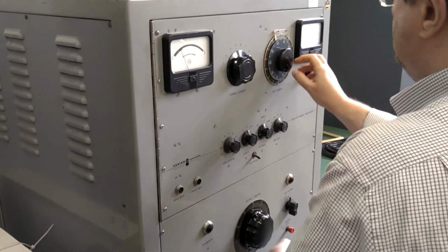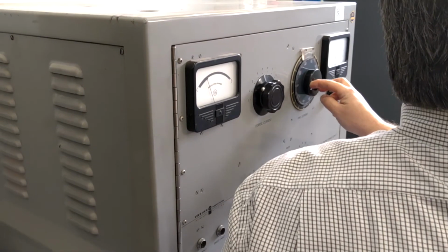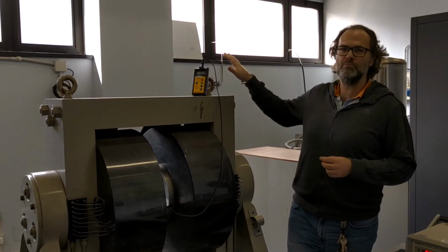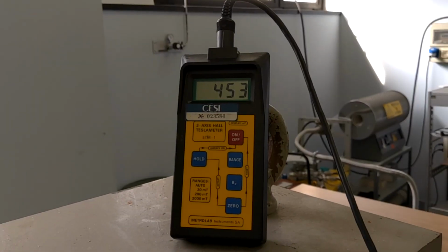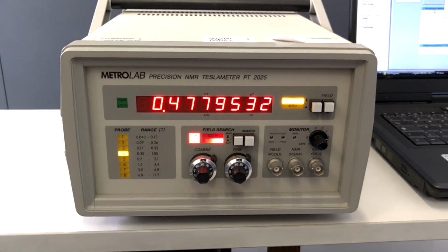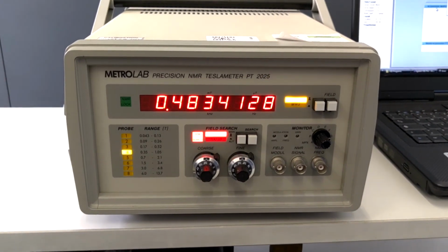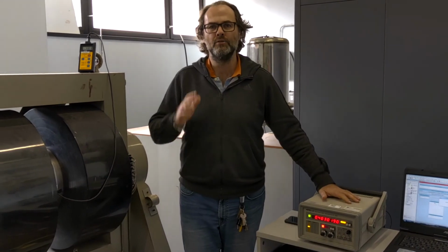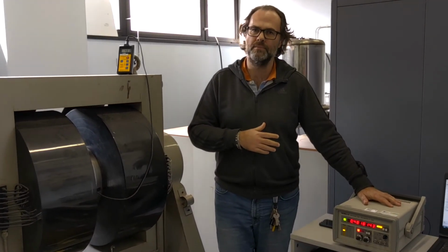The calibration is done by comparing the reference probe with the unknown probe at a certain number of applied field values. Now my colleague is powering on the magnet in order to reach a magnetic field of approximately 500 millitesla. He will use the Gauss meter to be calibrated as a rough guide for reaching the correct field value. Once the field is reached and is stable, the NMR instrument, our reference instrument, will match the precession frequency of the proton and will give us the reference value for the magnetic field, so we can compare the reading of the unknown instrument with the exact value given to us by the NMR instrument.